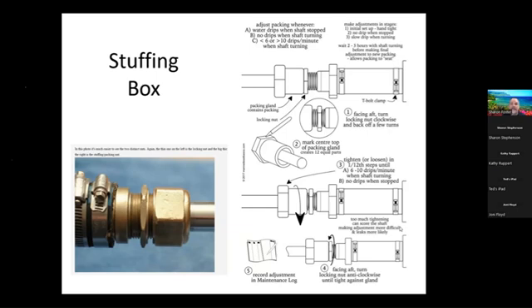All right. Now, if you notice, you got the small nut in behind here. That's your locking nut. So when you go to adjust this, you're going to have to loosen that up by turning it clockwise. All right. Then the larger nut in front of that is where the packing is. To tighten it, you're going to turn it clockwise. To loosen it, you're going to turn it counterclockwise. Then once you get it set to where you want, then you tighten that small locking nut back up against the jam nut, and you're all set.